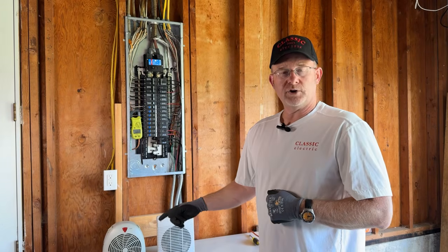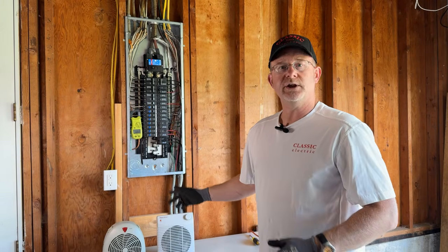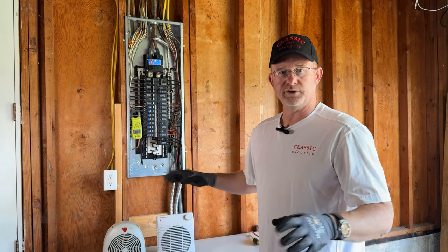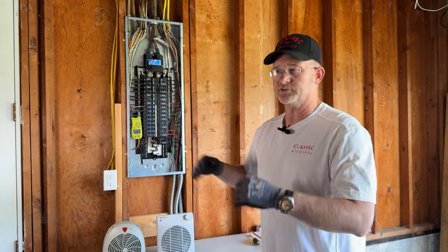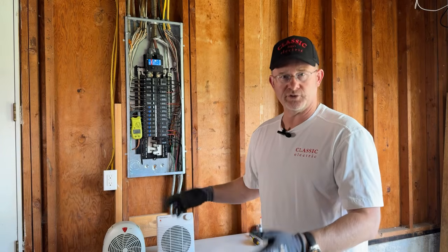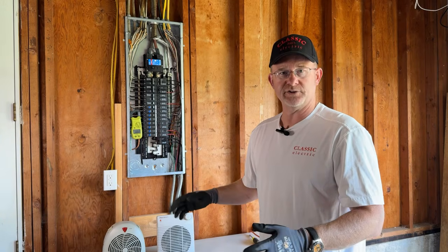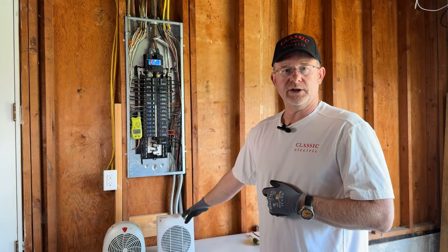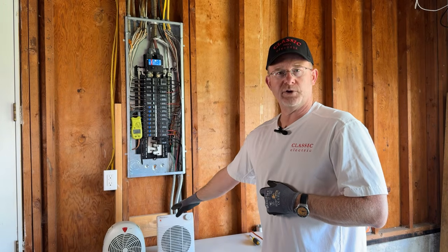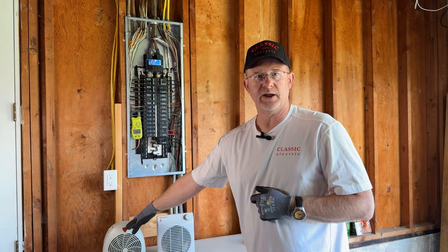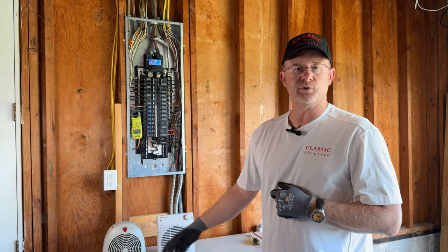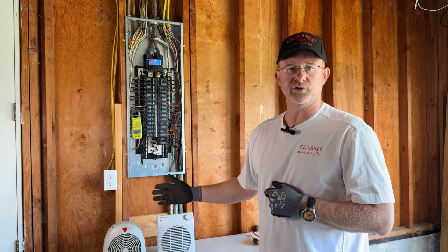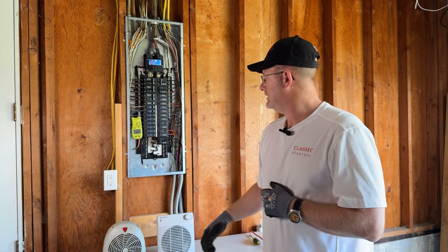The most common call I get is, hey, I've got two heaters in my living room. And usually that's where I stop listening because you've already told me everything I need to know. But I got two heaters in the living room and the circuit's tripping and it's not holding and I think I got too much going on and, can you give me some advice? Well, when you told me you got two heaters, I know that this thing's pulling 12.5 amps and this is pulling 12.5 amps. 12.5 and 12.5 is 25 and it's probably on a living room circuit that's 15. So I already know that it's overloaded and I know what the problem is.